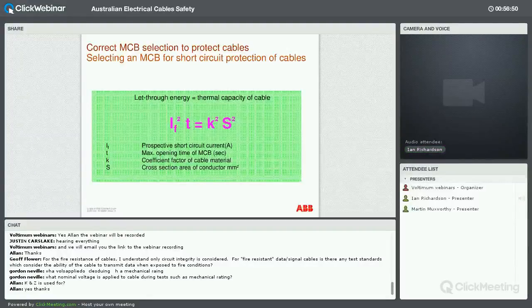So we don't want a slow operating breaker. In general terms, in our miniature breakers, yes, they do operate very, very quickly. As we get into the larger capacity breakers, they're not quite as quick, and there are some older technology breakers around which certainly won't operate as quickly.